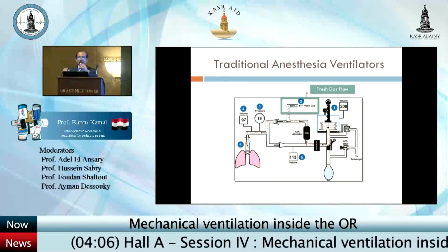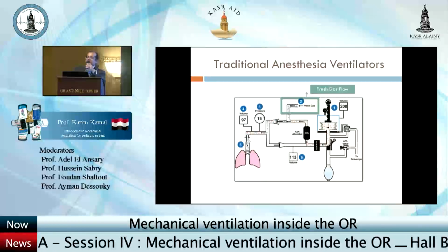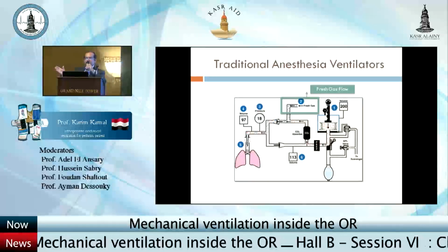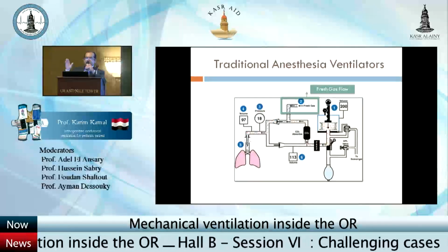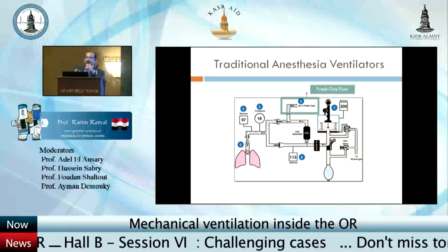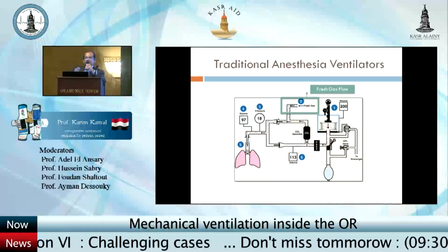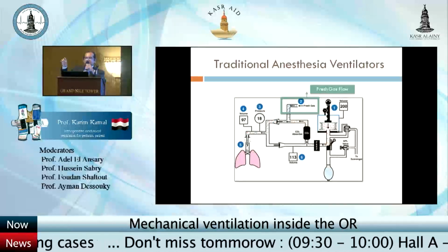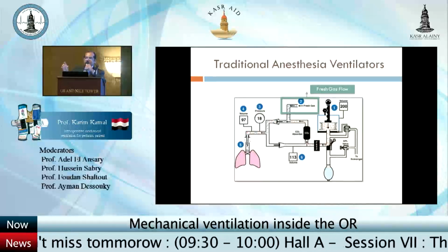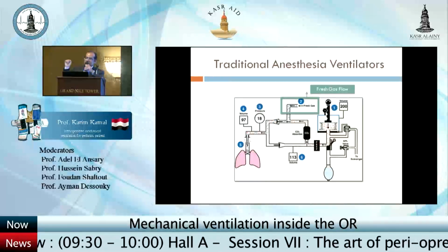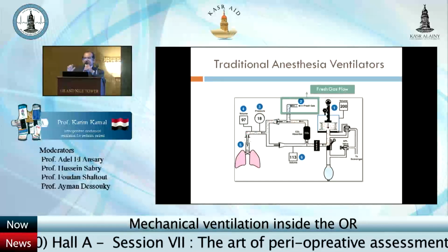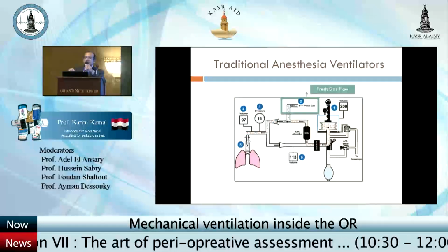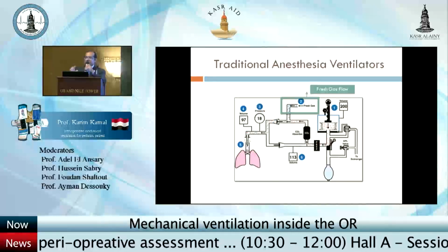The fresh gas flow inlet was placed between the bellows and the patient. So during inspiration, as the gas flowed through the breathing circuit, this gas was mixed with the gas coming from the fresh gas flow outlet.